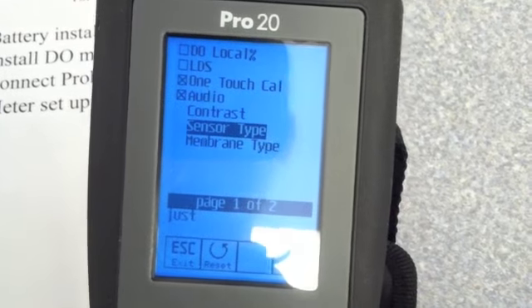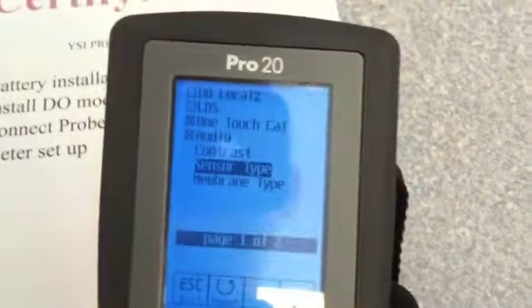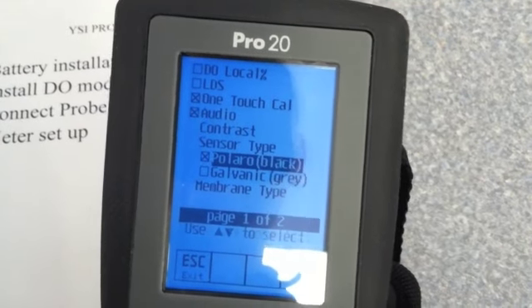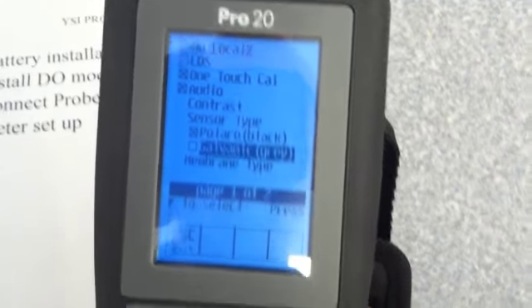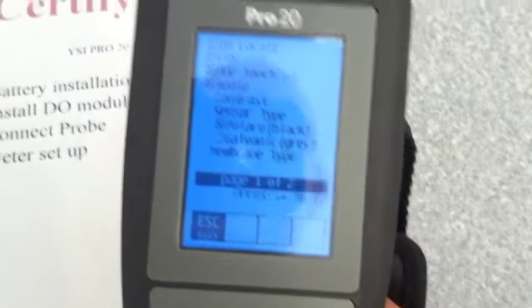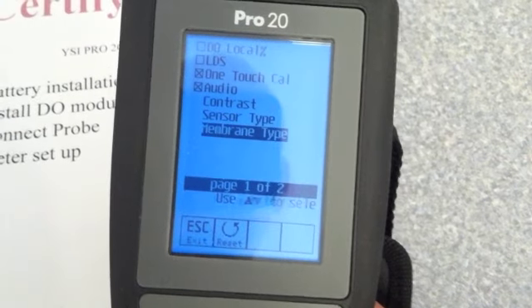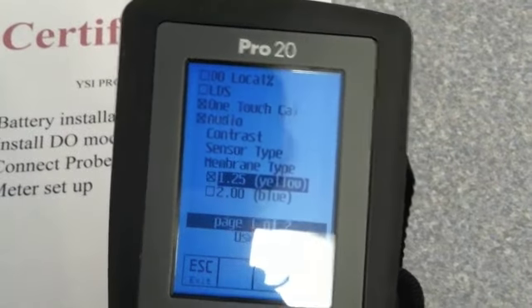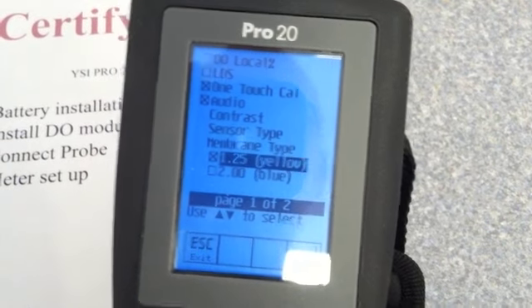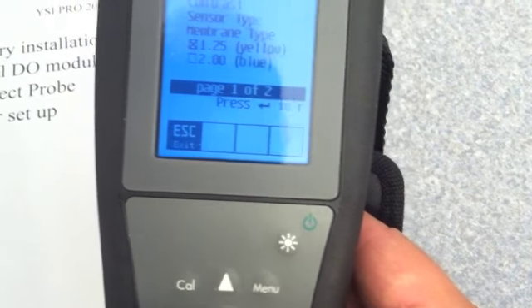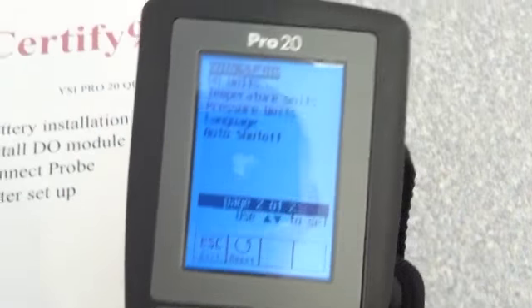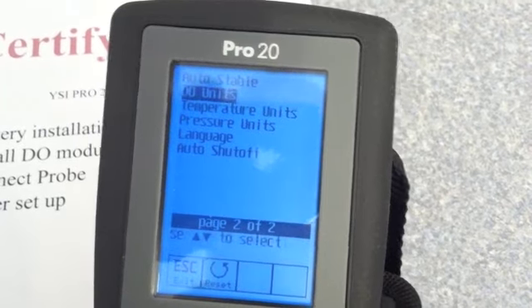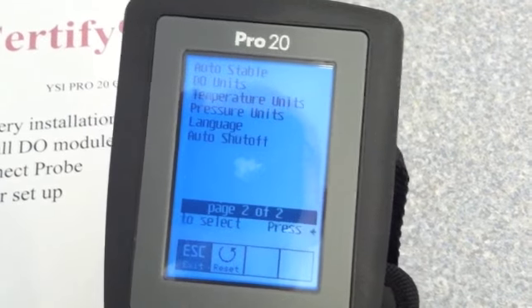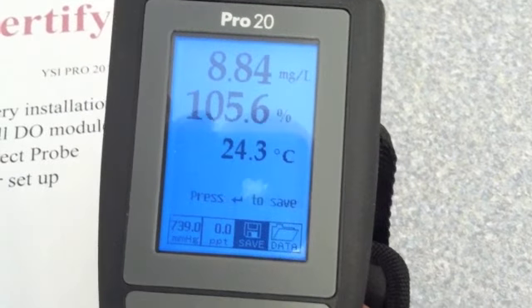Right here, we're going to verify our sensor type, so I'm going to hit the enter button, and like we ran through the menu system, it's at polarographic black. So then we just want to keep hitting the down arrow until we see escape, and then we hit the enter button, and then it takes us to the next line, which is the membrane type. And if we hit the enter at that point, we're going to see that as we were doing the setup originally, that it's at yellow. So again, if you ever get lost, just keep hitting the down arrow until you see escape, and then when you hit enter, it takes you to the next line, and let's just run all the way through back down to escape, and then we'll be back into the menu system.